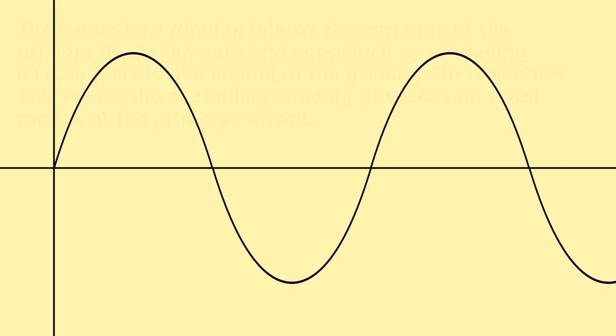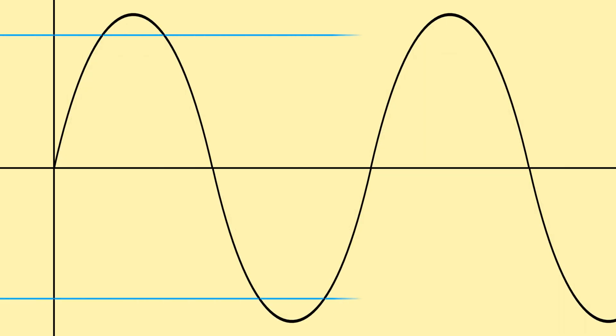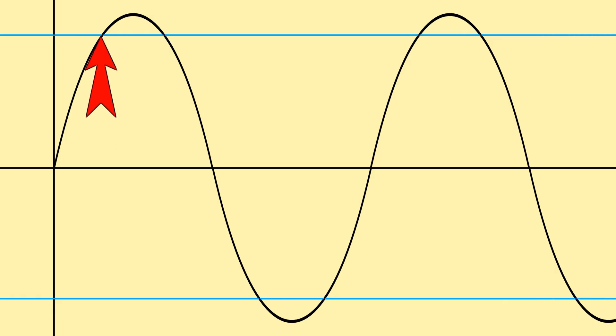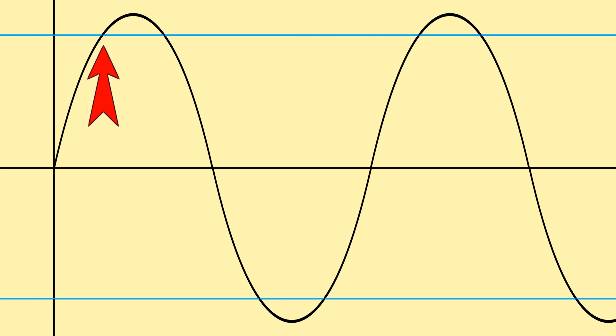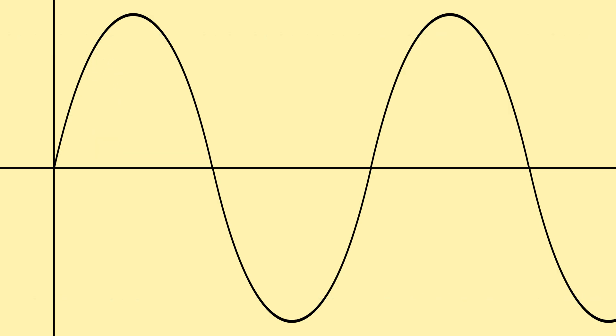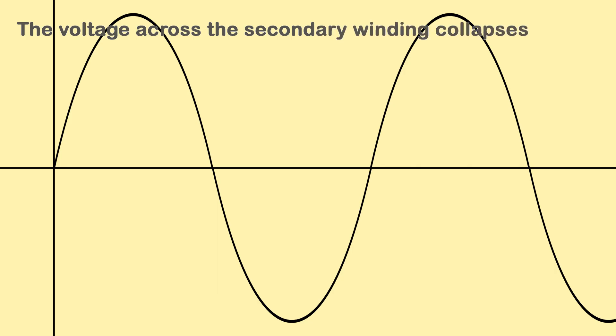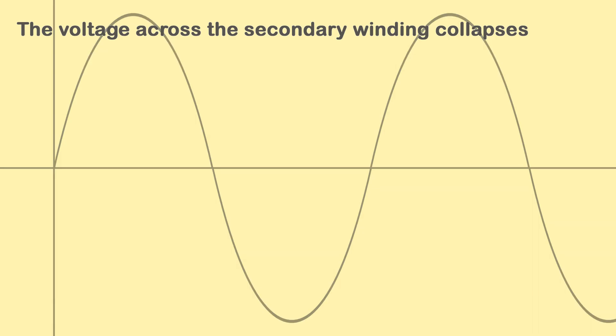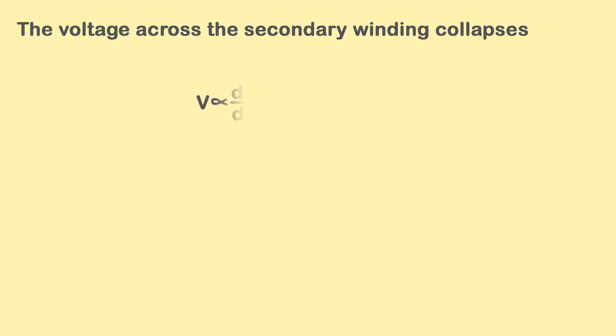Now suppose the primary current increases. After a certain value of the primary current, the CT core becomes saturated. This means the primary current can no longer produce flux beyond the maximum flux-carrying capability of the core. As a result, the primary current stops producing additional flux at that magnitude, and there will be no further increase in flux. Hence, the flux waveform becomes flat from that point. Consequently, the voltage across the secondary winding collapses, because according to Faraday's law, the induced voltage is directly proportional to the rate of change of flux linkage with respect to time. When this rate becomes zero due to core saturation, no voltage is induced in the secondary winding, leading to voltage collapse.